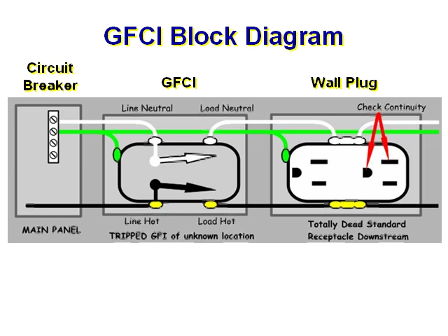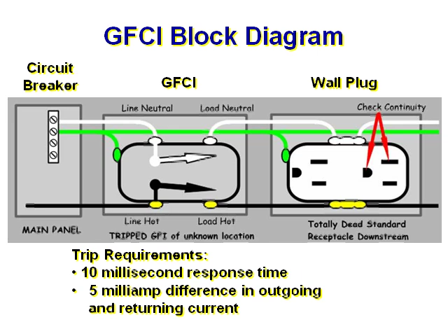It contains switches in both the line neutral and hot electrical lines. It is capable of completely disconnecting the wall plug from the two possible power sources. The GFCI only responds if there is a difference in the outgoing and returning line currents. It will not respond to a short in the circuit. The circuit breaker is designed to protect the circuit against shorts. The GFCI is required to trip in 10 milliseconds on current differences of 5 milliamps.